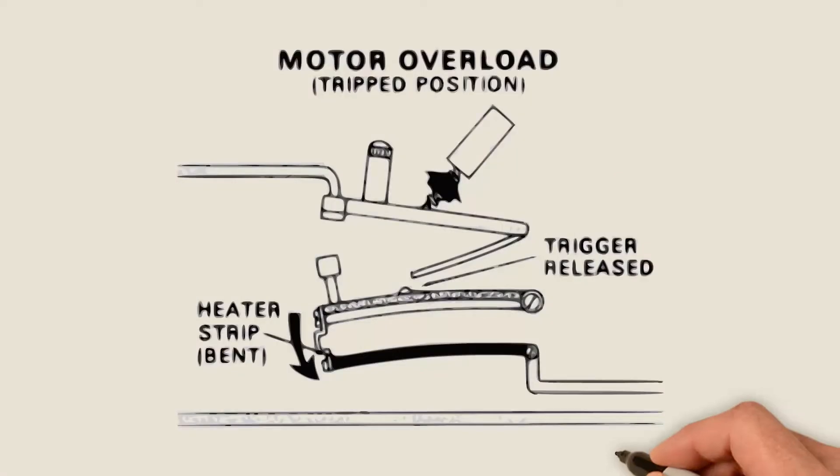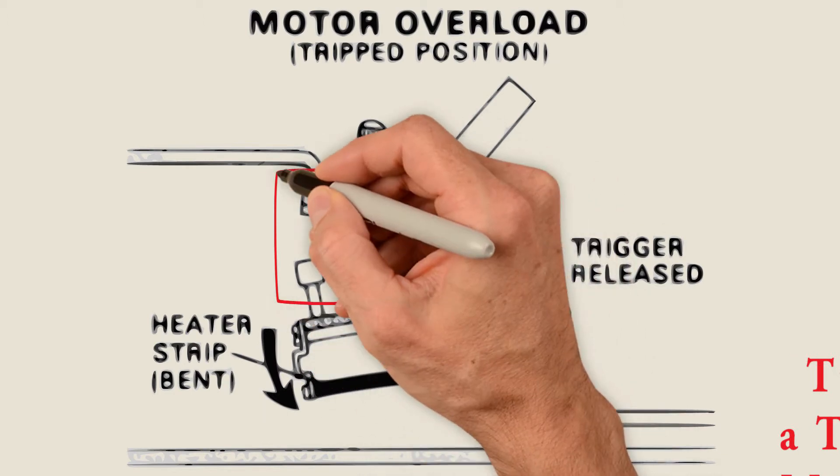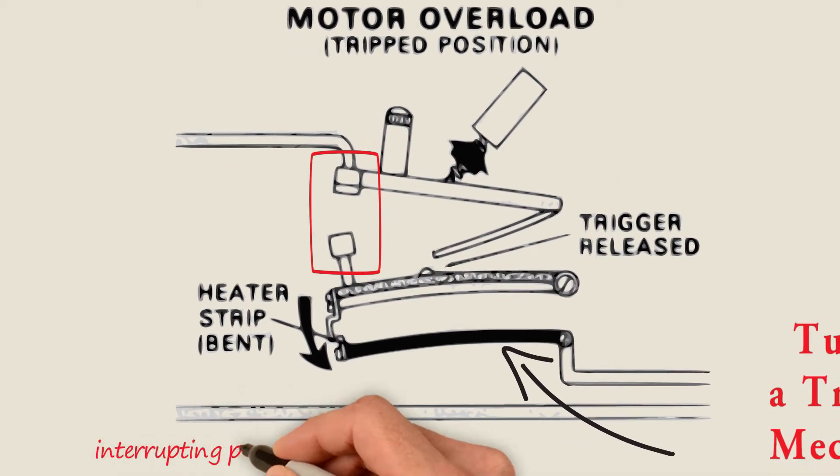When an overload occurs, the heat causes the bi-metal to deflect and turn on a tripping mechanism which opens a set of contacts in the control circuit, interrupting power to the coil and opening the power contacts.